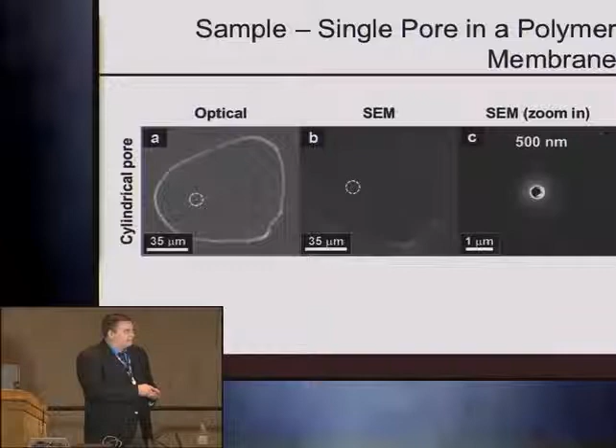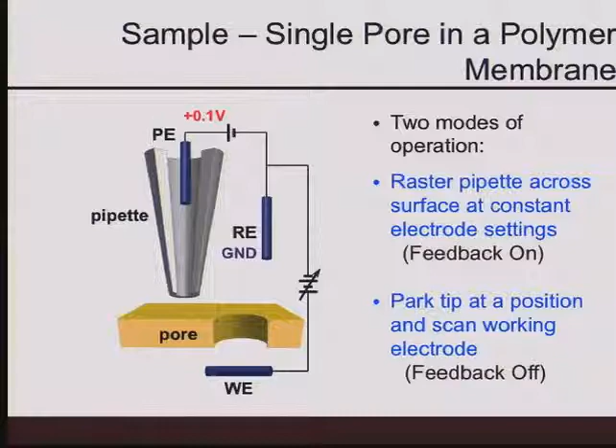Okay, there are two ways to make these kinds of measurements then. The first way is that we're going to take the tip and we're going to raster it across the surface in an imaging fashion. When we do that, we hold the pipette electrode at a constant potential, and we hold the working electrode at a constant potential. So the only thing we're looking at then are differences in the spatial conductance profile. The other thing that we can do is if we find a spot, for instance, over a single pore, where we see changes in the conductance, we can park the tip at the pore and scan the working electrode potential. And when we do that, we turn the feedback off so that the position of the probe doesn't move up or down. So the probe's locked in position relative to the pore. And we're just looking at the influence of these two electrodes on each other relative to the reference electrode. When we raster the surface, we obviously have to have the feedback on that maintains a constant tip sample separation.